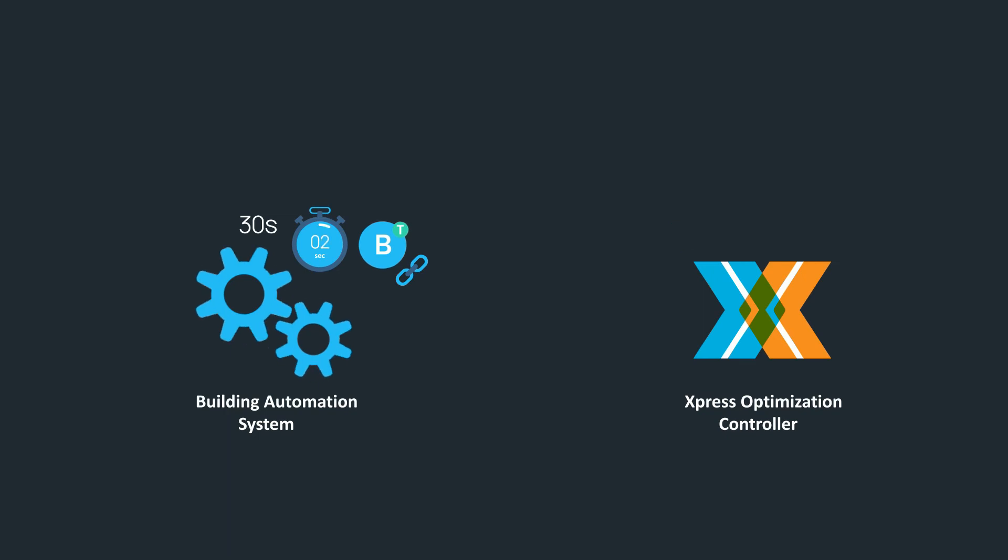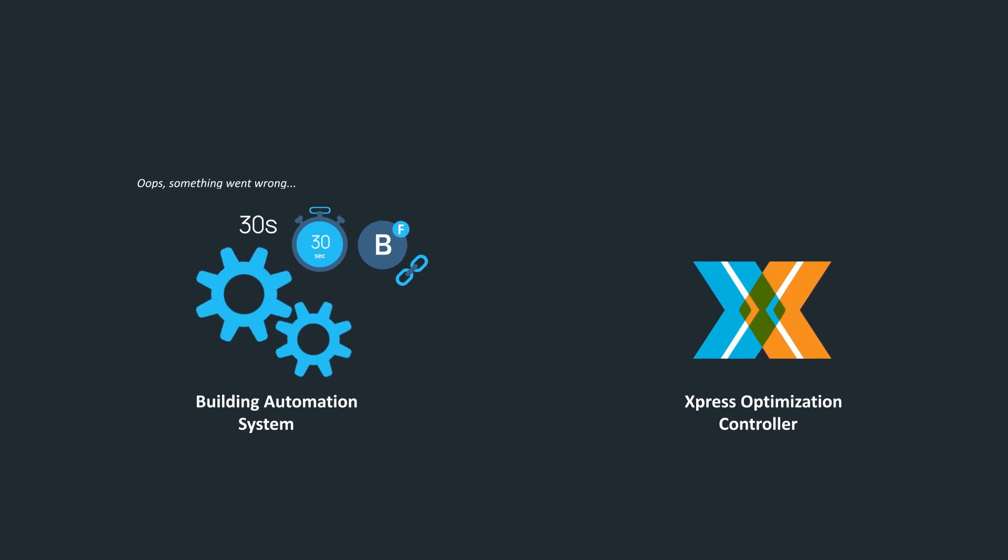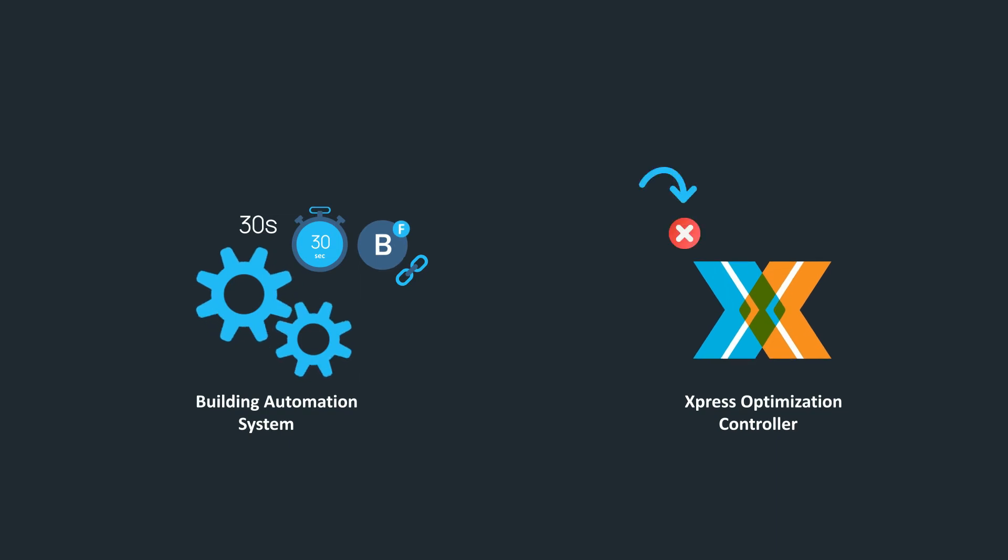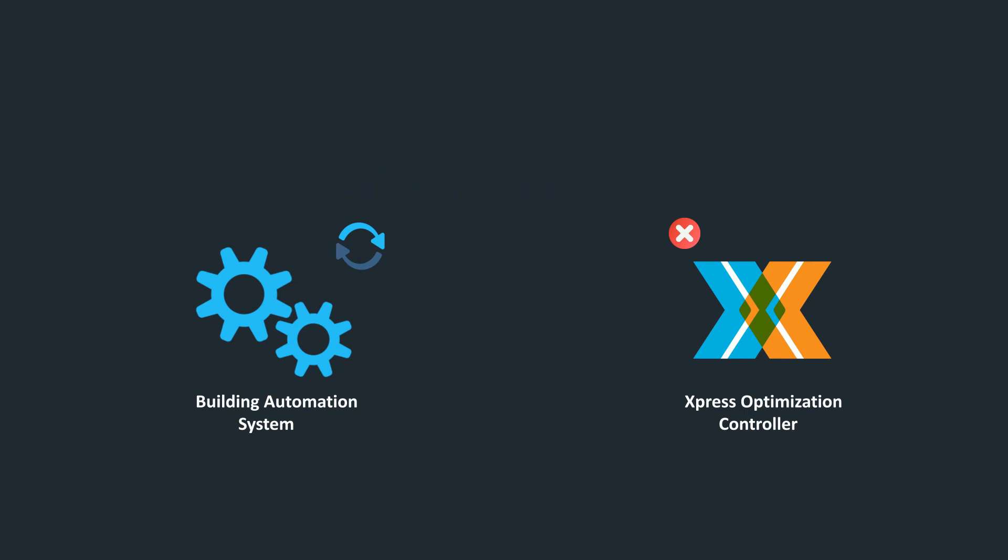What exactly does the Xpress Optimization Controller do with your BAS pulse? Well, when the Xpress Optimization Controller detects that your pulse has stopped toggling for any reason, it will hold optimization and your BAS program needs to execute the bumpless transfer sequence into the standard sequence of operation. Don't worry, more on how to program that component later in the Bumpless Transfer Programming video.